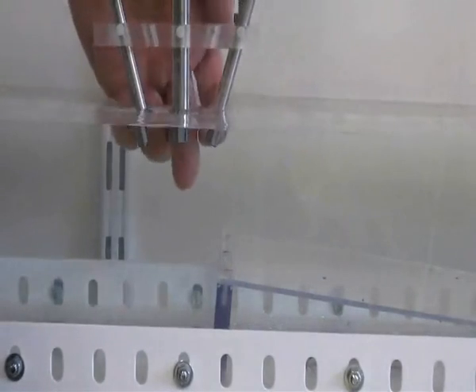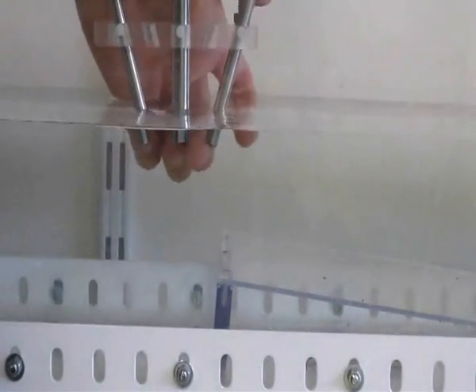The way the transducers are arranged and the type of transducers comes from the simulation software. Be sure that no air bubbles are attached to the transducers.